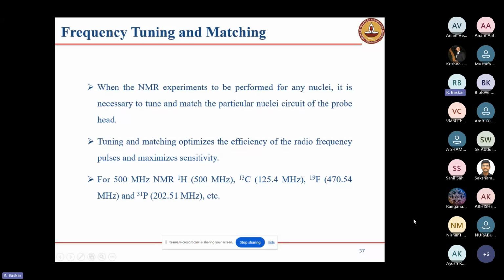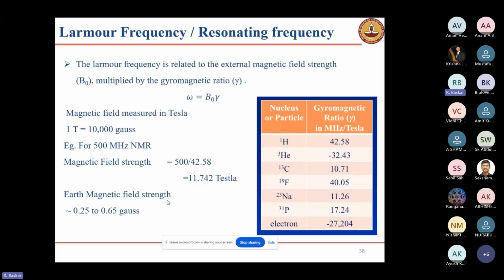Tuning and matching optimize the efficiency of the radio frequency pulses and maximize the sensitivity. For example, in 500 megahertz NMR, if you want to do the proton, we have to give exactly 500 megahertz radio frequency. If we give another frequency, we won't get the NMR signals. How are we calculating this? This is called the Larmor frequency or resonating frequency. How are we calculating? This is the formula.